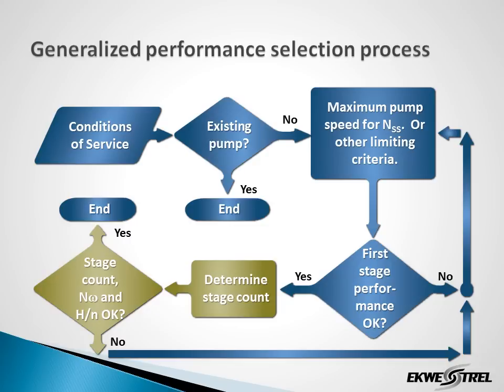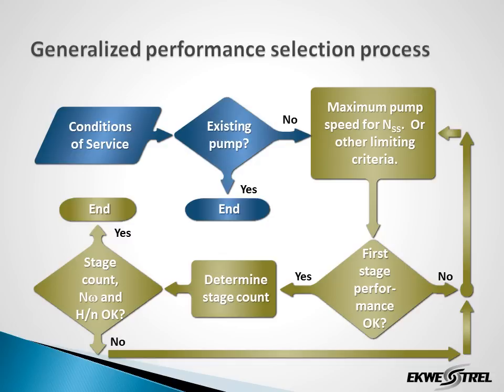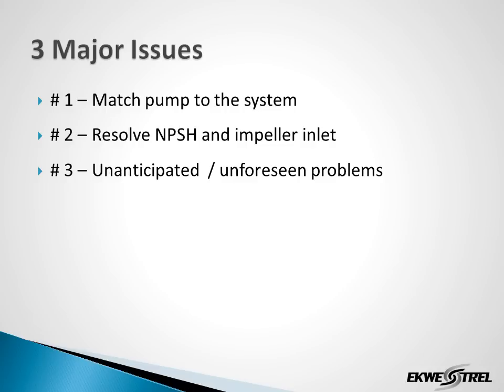Returning to the pump performance selection process, when the speed is selected and after checking the first stage performance, the stage count is resolved. There is actually a whole iterative process that happens involving the speed selection, determining the first stage performance, and resolving the stage count. To recap, we have the three major issues: matching the pump to the system in order to avoid oversizing the pump; resolving the NPSH and impeller inlet — which is also an oversizing problem if we provide too much margin, especially for the run-out flow, then we oversize the impeller inlet; and unanticipated and unforeseen problems.